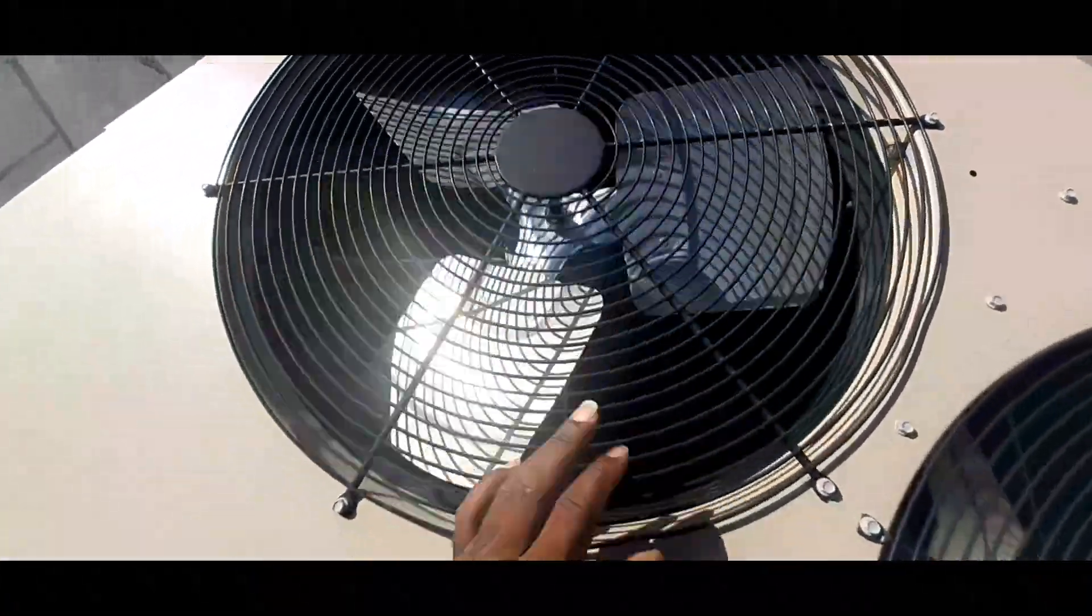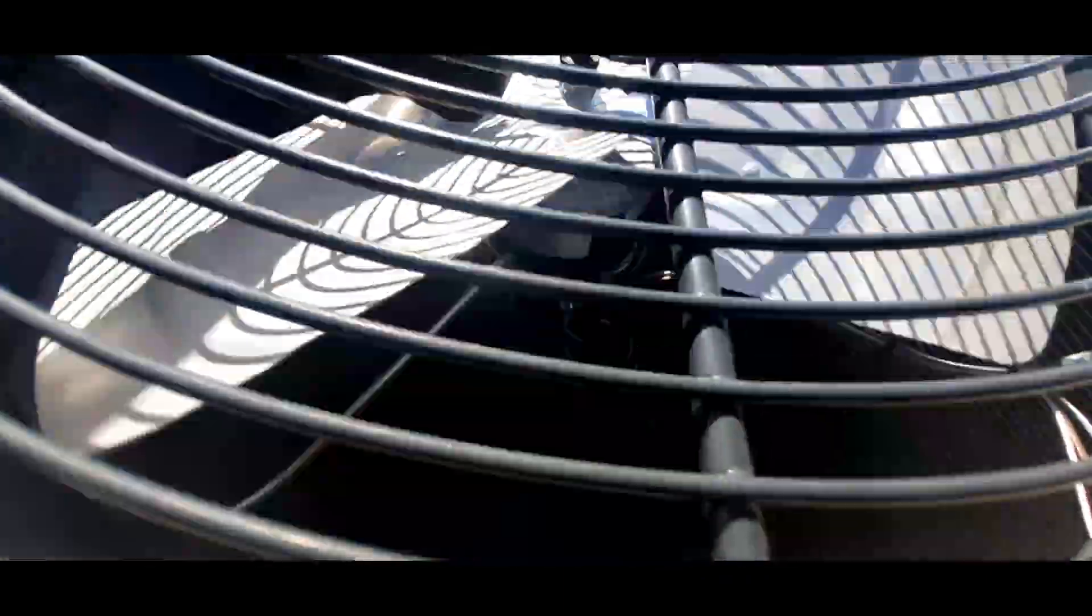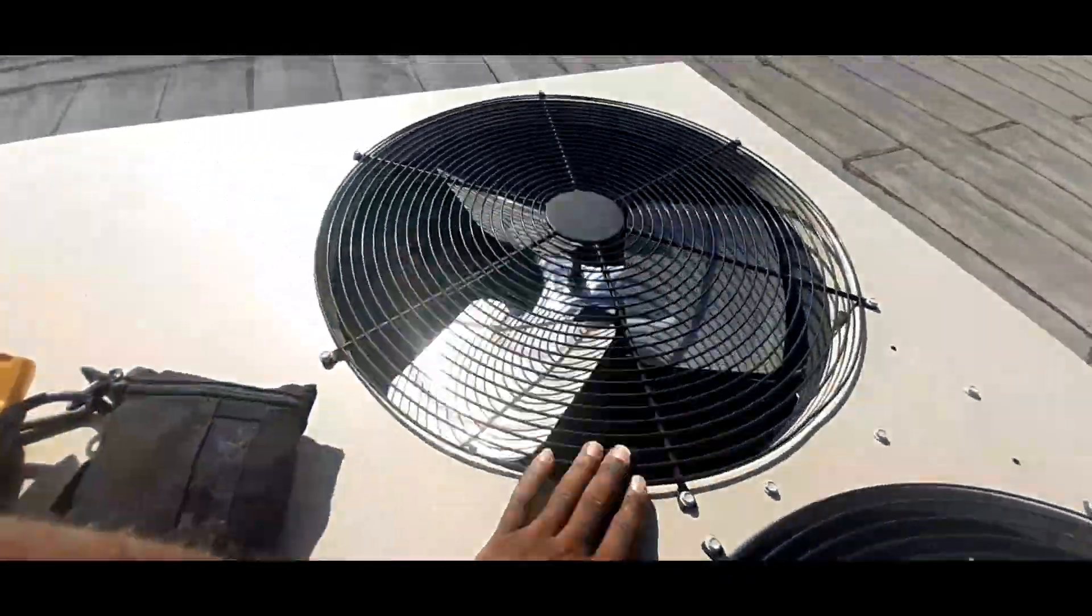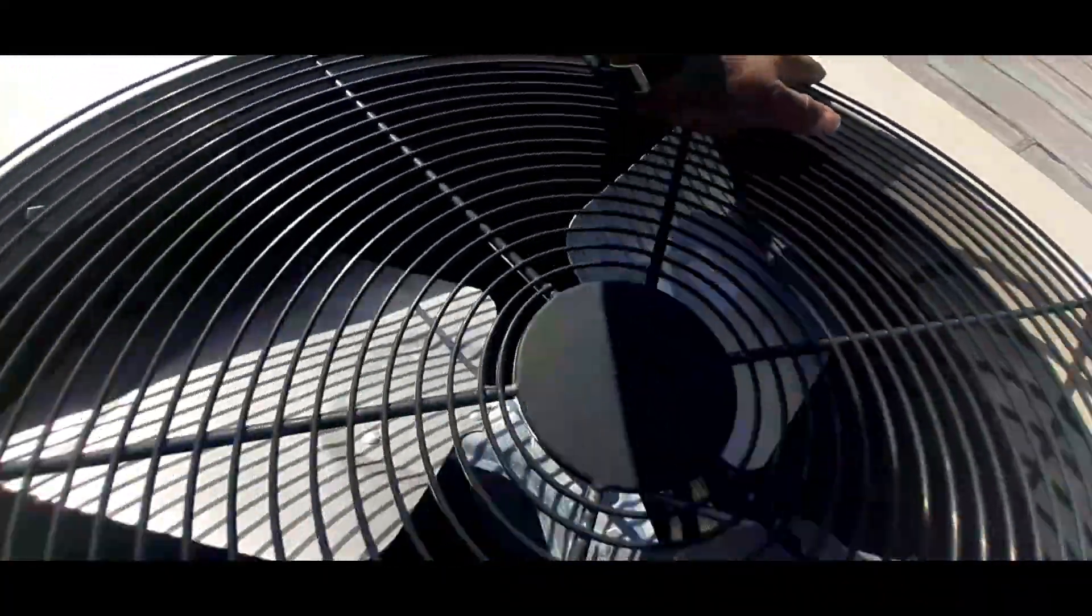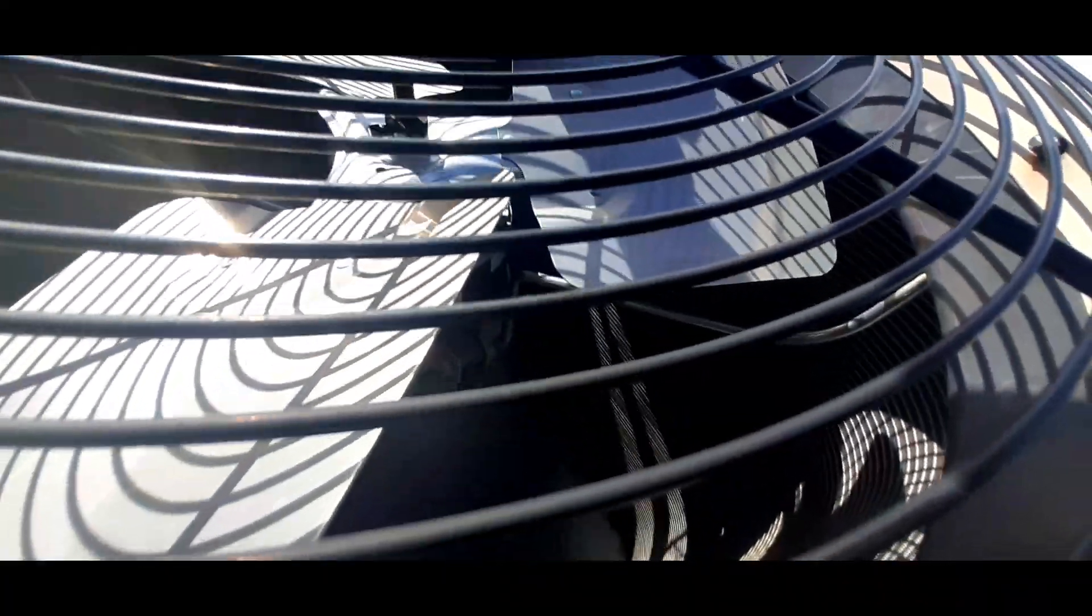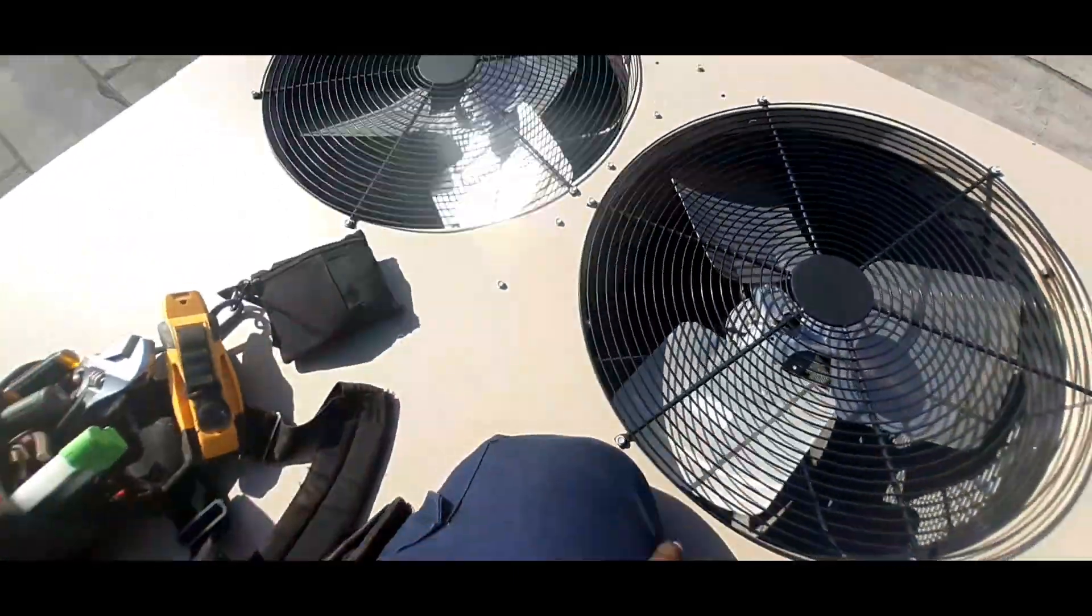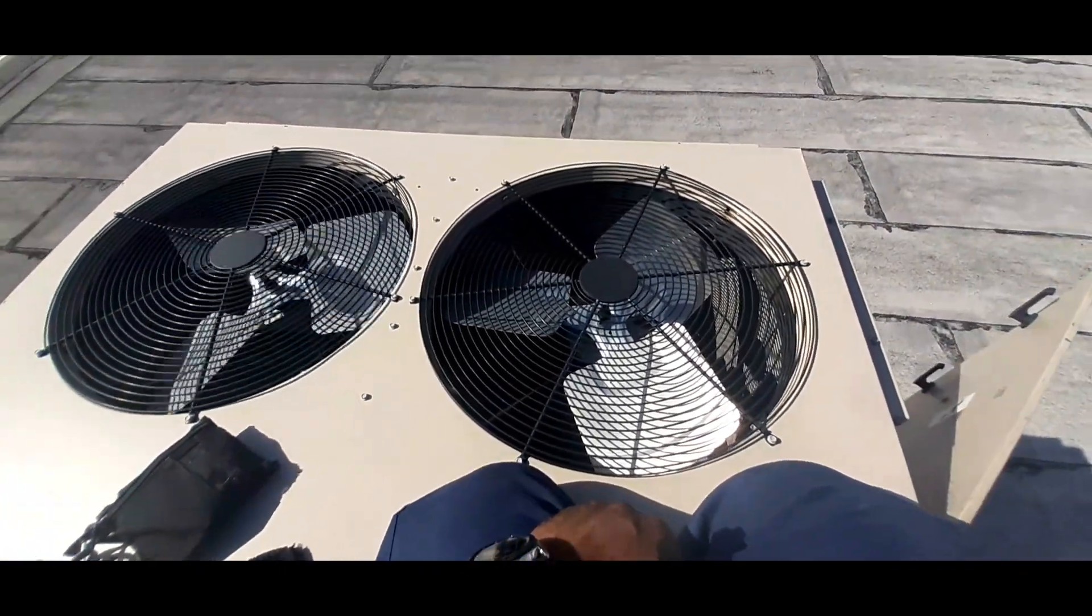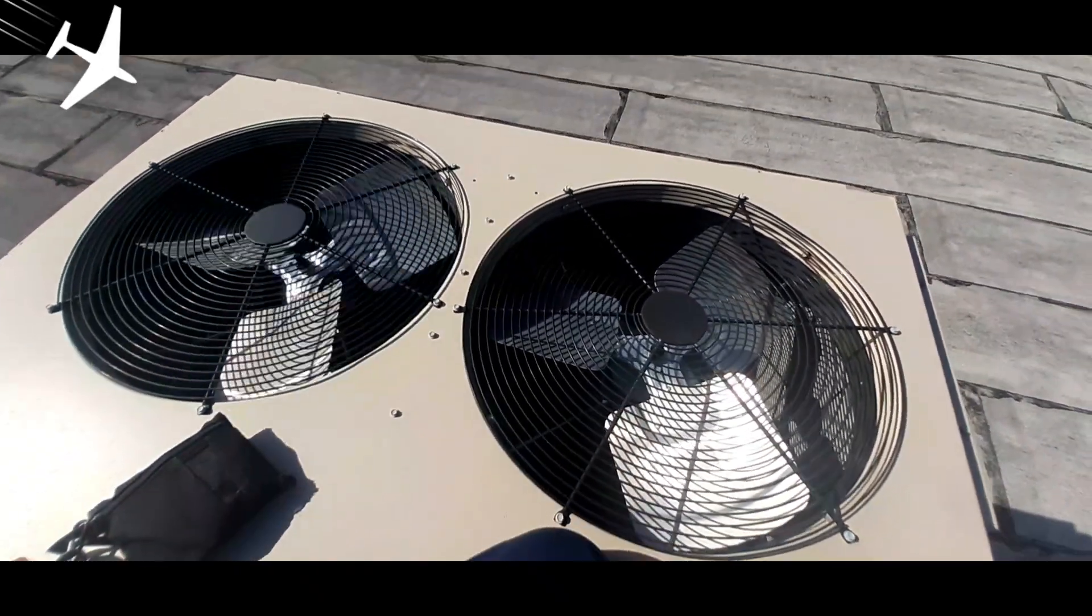All right, so I just climbed up on top of the unit. I'm just looking for any burnt marks, anything. Those plugs look pretty good. Look how fast that one is spinning compared to this one. This one might be our problem. Look at those wires down there. Those connectors look pretty charred, some discoloration. And like I said, look how that one's free spinning and this one just stopped in the middle of thin air. This one here is going to be our problem.